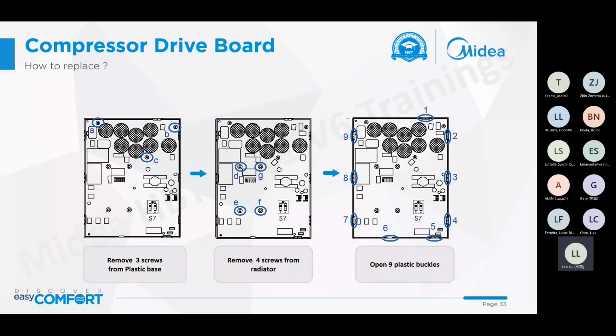Okay, as we know, the compressor drive board is something we usually need to replace. It is very easy to damage because the compressor drive depends on many factors. For example, the temperature is too high, or the environment is not very good because there is a lot of dust and humidity. These usually can cause the compressor drive to be damaged, and usually we need to replace it. As we know, usually it will display H6, P6, H4 protection. Usually we need to replace the compressor drive board or the compressor.